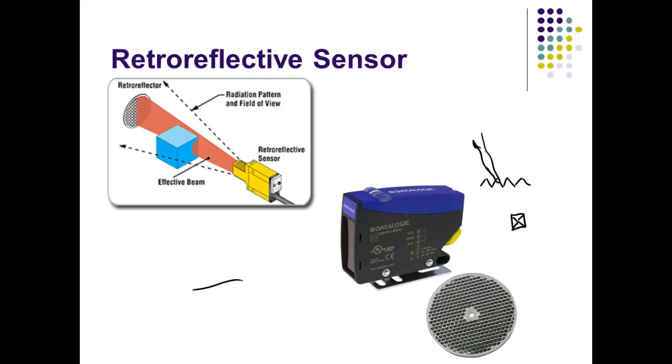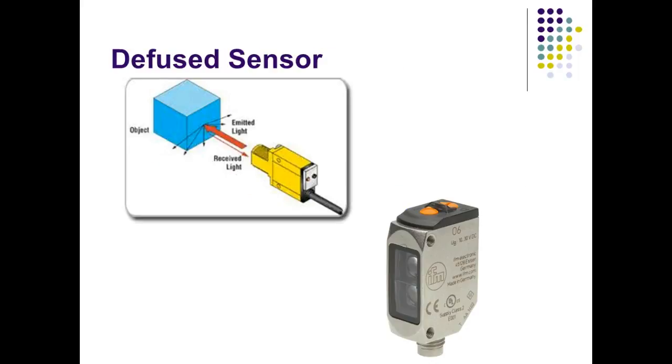These are what we call retroreflective sensors. So what's happening is they're depending on the light to go over, hit the reflective sensor, and then bounce back. Now, these are a little cheaper, a little easier to maintain, and a lot easier to adjust, but they don't have the sensing distance of the through the beam sensor. We have a lot of these on the manufacturing line over there, and we'll go over there and look at all these photoelectric sensors.